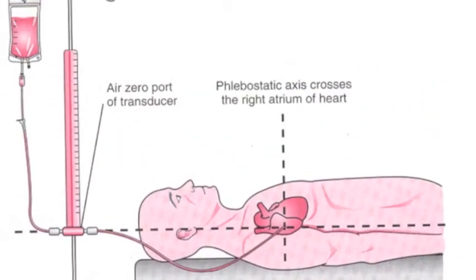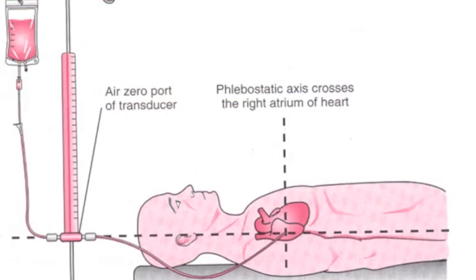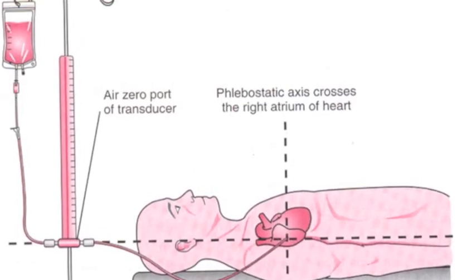So that's our zeroing. The next step we're going to do is level. And in order to level your arterial line, we need to look at a point called the phlebostatic axis. So let's go take a look and see what that looks like. So here we have a nice picture of where the phlebostatic axis is in relation to your patient's heart anatomy. Now your phlebostatic axis, we basically use it as a reference point. It approximates the level of your right atrium. And in our facility, we actually use the patient's arm to allow us to level the transducer at that point. You can also have it on a separate holder, but we, for convenience, put it right on the patient's arm.